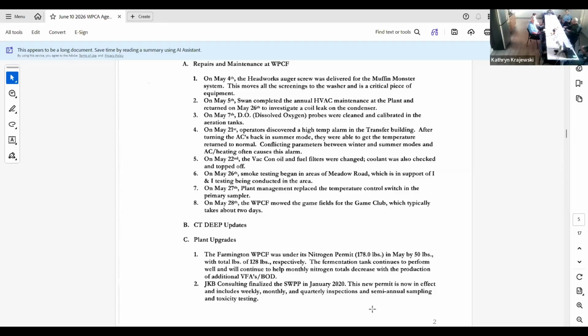Swan completed annual HVAC maintenance at the plant, and we may have a possible coil leak on the condenser in the maintenance shop, but we'll know more shortly. The dissolved oxygen probes were cleaned and calibrated in the aeration tanks. We had a high temperature alarm in the transfer building on May 21st. That's an HVAC issue where in the winter program the heaters kick on, and in the summer the AC kicks on, but there are also louvers that can pull outside air in. Sometimes when it's those nights that are 40 and it's 80 in the day, the program gets thrown off, so we basically just reset it and we're back to normal.